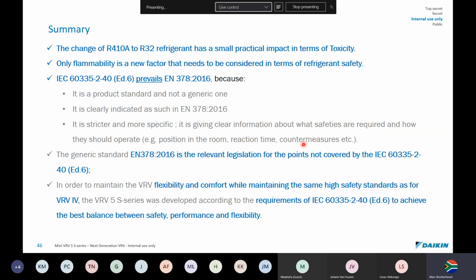And I just want to summarize what I've got. In summary, the change from 410A to R32 refrigerant has a small practical impact in terms of toxicity. 410 is just as dangerous as R32 when it comes to being toxic. Only flammability, R32's flammability, is a new factor that needs to be considered in terms of refrigerant safety.